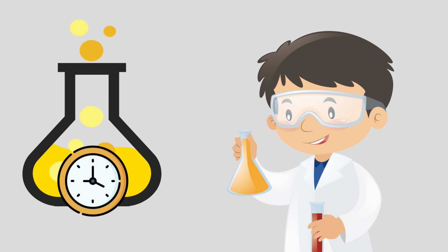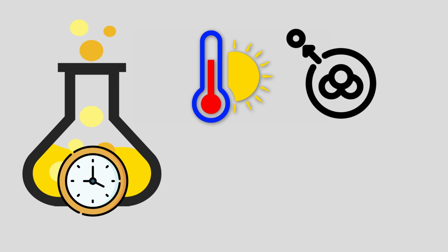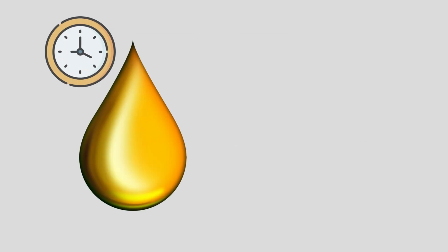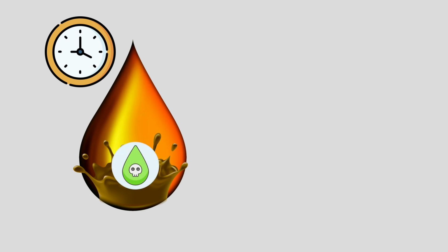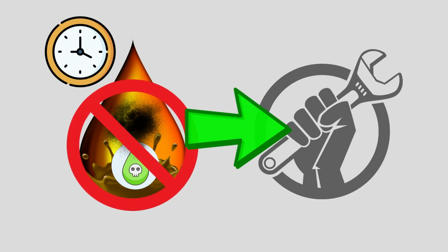In particular, turbine oils shall have high resistance against air oxidation at an elevated temperature, high demulsifying ability, and low initial acidity and ash content. Furthermore, no particulate matter is allowed. However, during operation, aging of turbine oils occurs, the result of which is an increase in their viscosity, acid number, particulate matter and ash content. The use of such oils can lead to alarm conditions, shutdown, long downtime, and expensive repairs of power turbines.